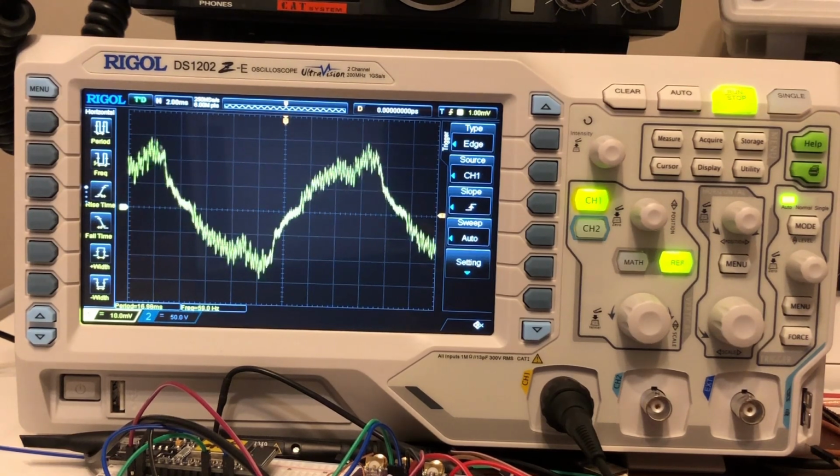When the two analog channels are used to acquire data, you can connect the trigger signal via the external trigger connector and use the signal as the external trigger source. AC line. The trigger signal is obtained from the AC power input of the oscilloscope. AC trigger is usually used to measure signals relevant to the AC power frequency. For example, stable trigger of the waveform output from the transformer of a transformer substation, and is mainly used in related measurements of the power industry.